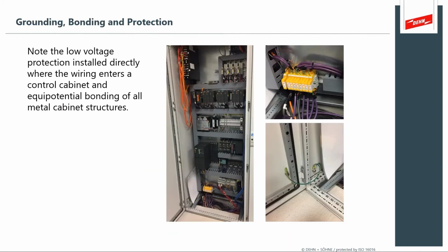Grounding, bonding, and protection all go together. If you can't bond your power wires, you have to protect the power wires, and that controls the voltage across the panel. These are the types of elements you're looking for, things like these bonding wires across the doors, so that the door doesn't have a voltage rise or get left behind.